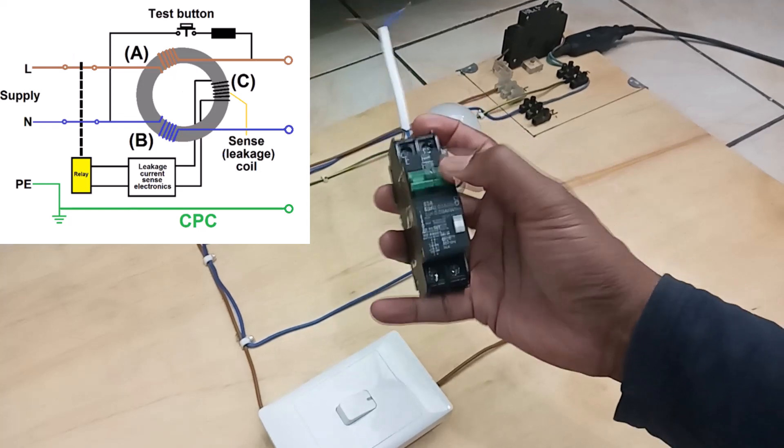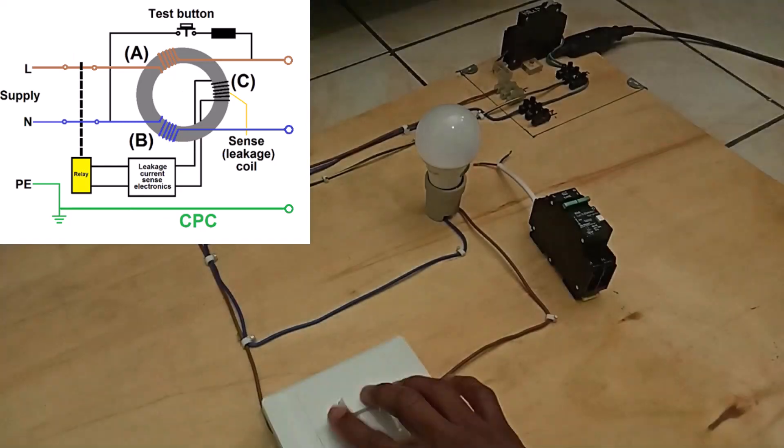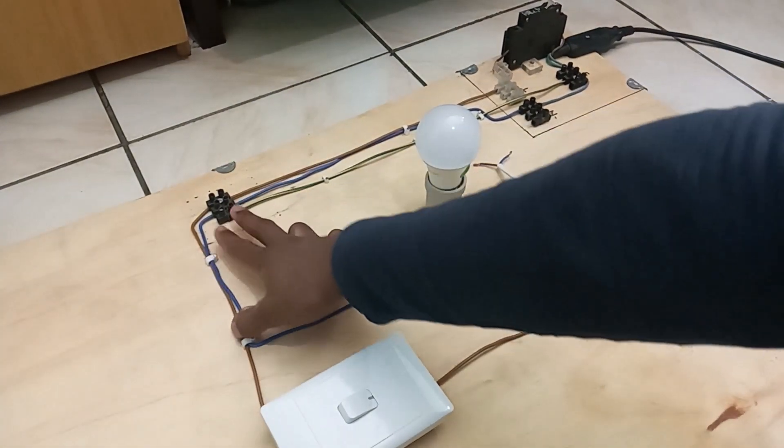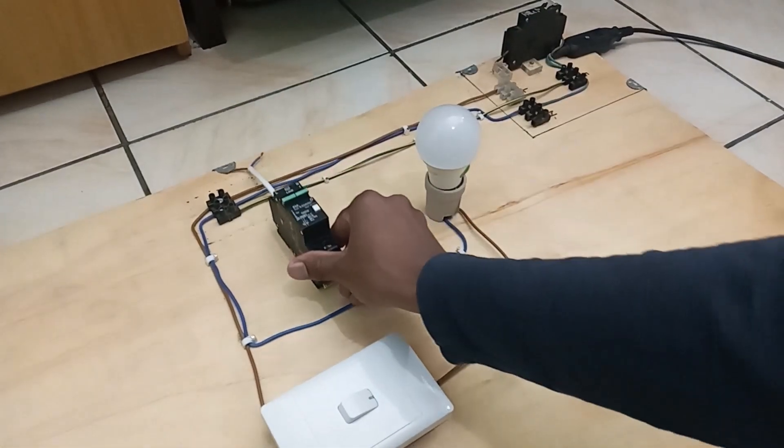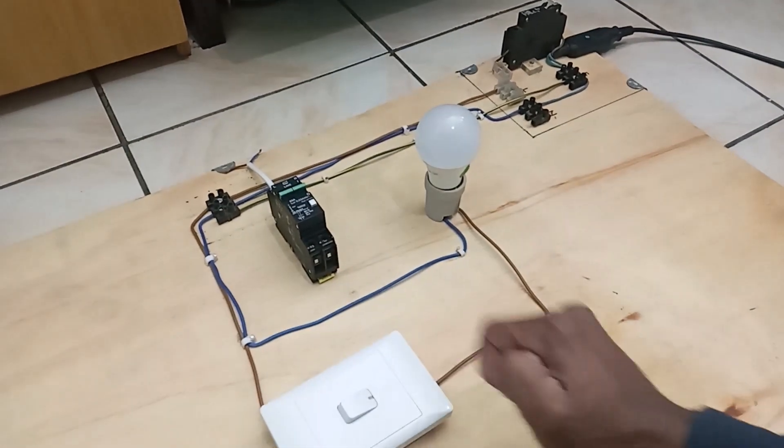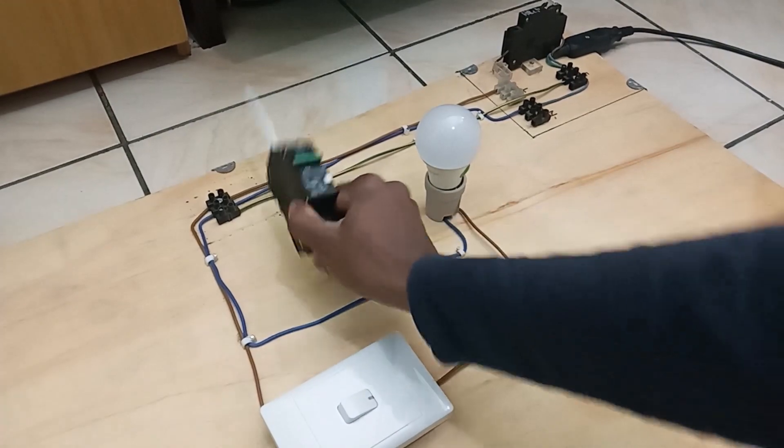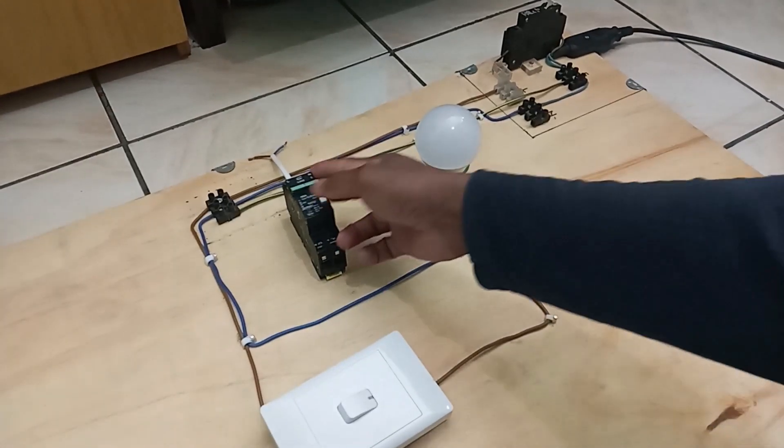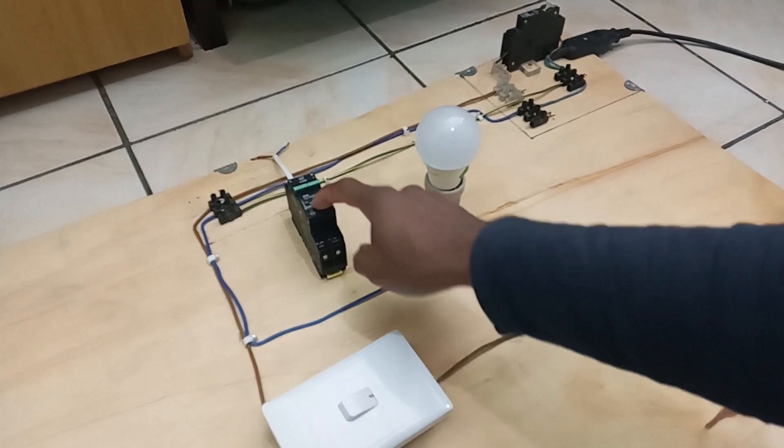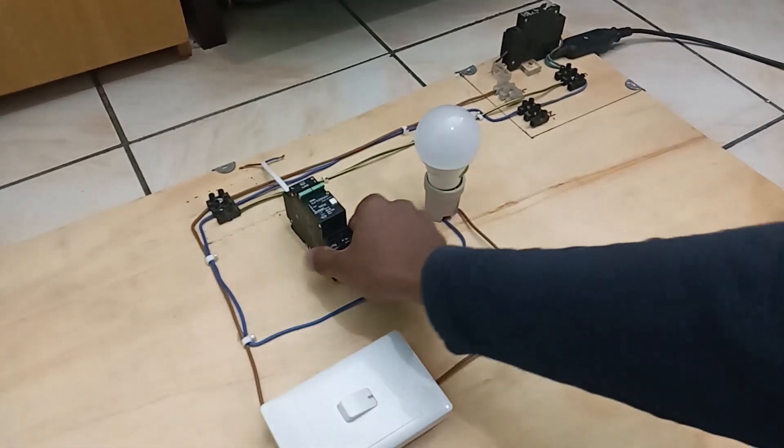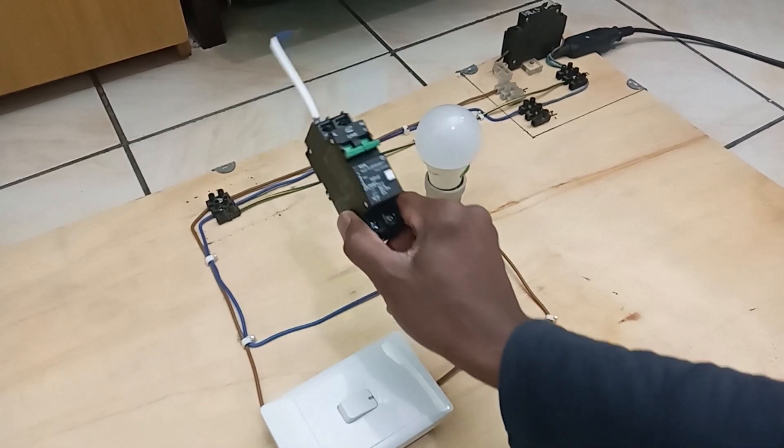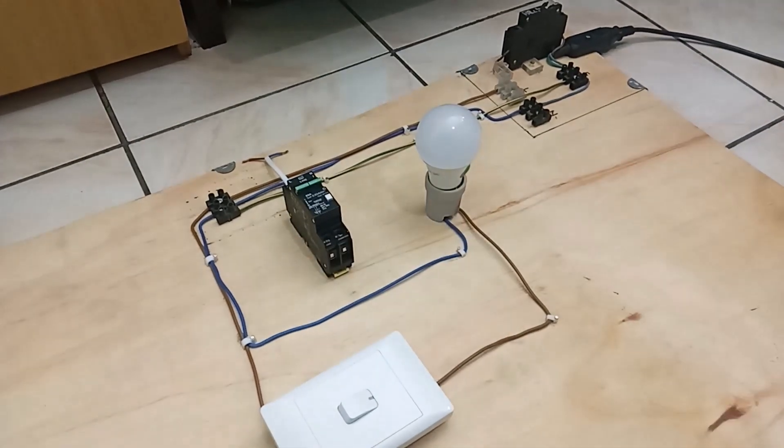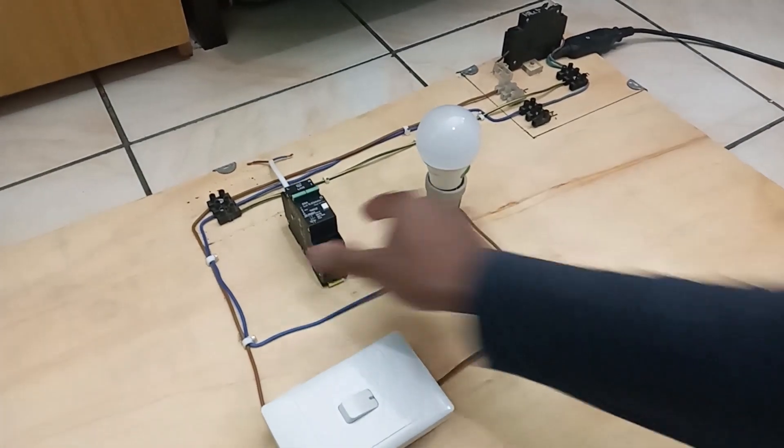So what I'm gonna do here in this circuit, I'm going to break the circuit here at the choc block, and I'm going to insert the leakage breaker inside with my circuit to feed into my light switch. So then the leakage breaker will receive power and will be energized. That way, when I press the white button here, the circuit should be able to trip. And if it doesn't trip, then I know this leakage breaker is not in good condition. So let's go ahead and do just that.